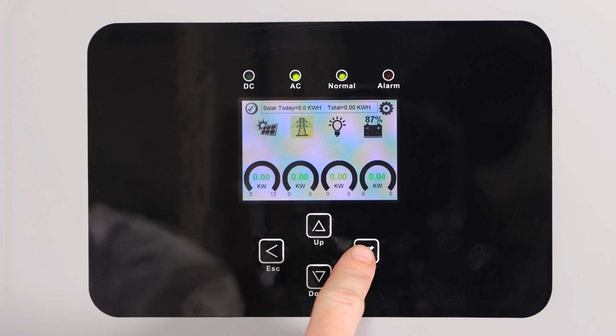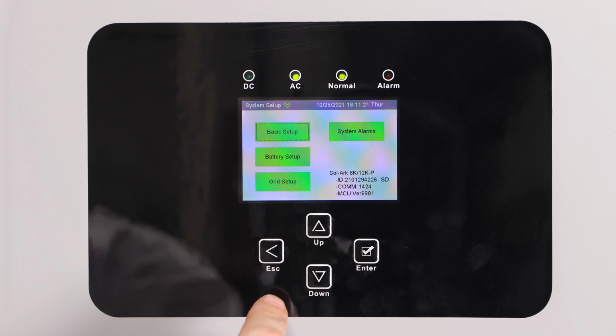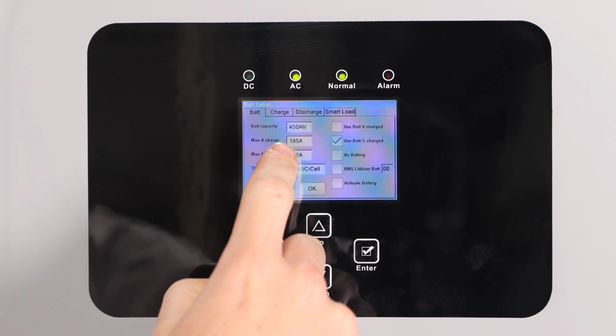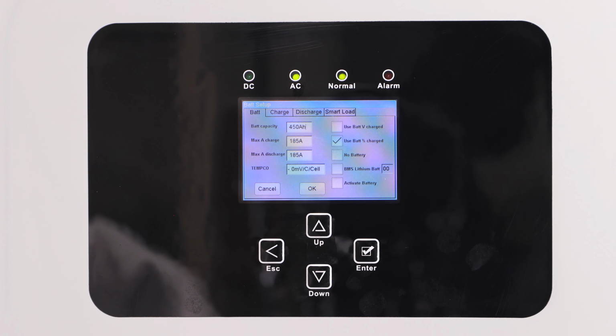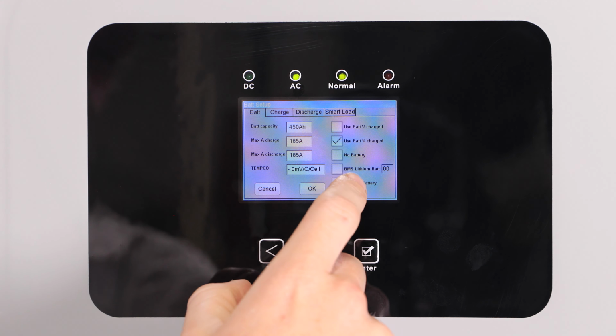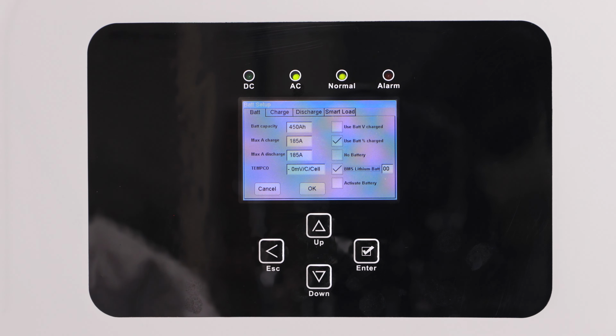First, navigate to the System Setup screen by pressing Enter, and then click on the Battery Setup tab. On the Battery tab, check the BMS lithium battery box and set the address to 00.